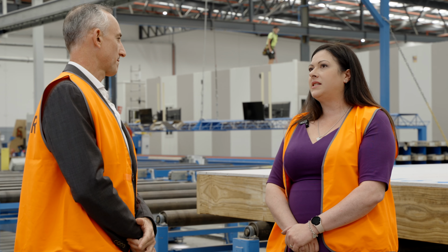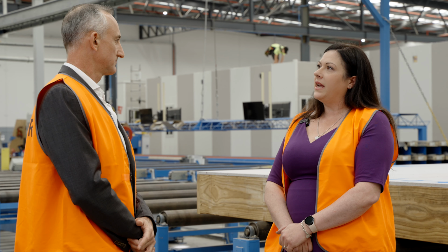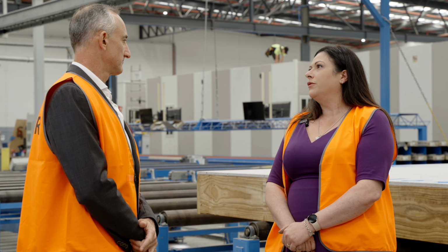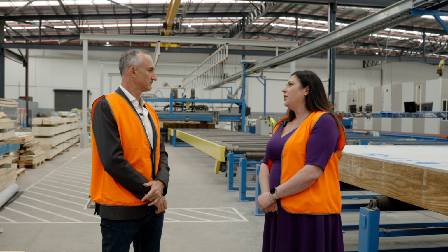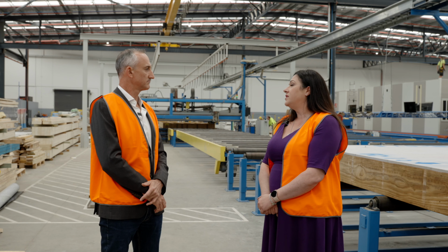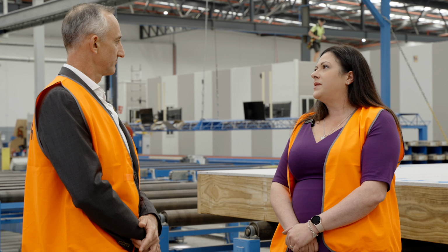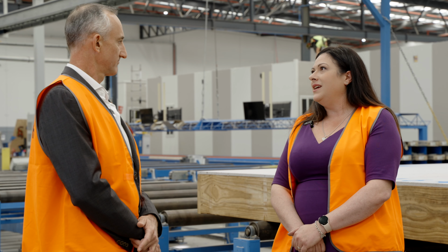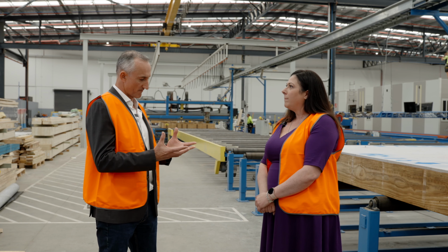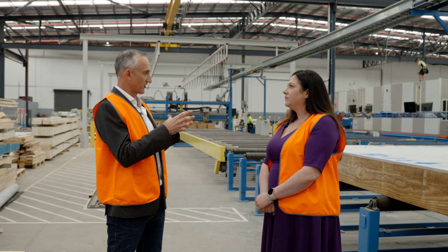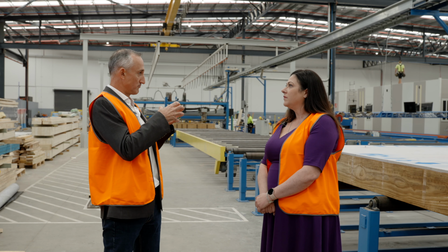Out of those components, I guess we've got the thermally broken double glazed windows. That stops the heat transfer from the external to the internal, cooler in summer and warmer in winter. Then you've got the double layer of insulation, so the minimum insulation in New South Wales is currently R2. We've gone for R4. And then the internal air tightness layer, which keeps that cooled and heated air in the building. You're not losing any of those benefits from all the other components in the building. So whilst the envelope is thermally protecting the internal occupants from the elements outside, the internal air tightness layer is stopping that conditioned air from moving from inside to outside.